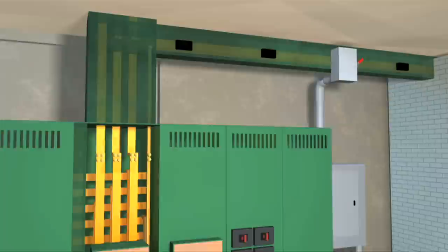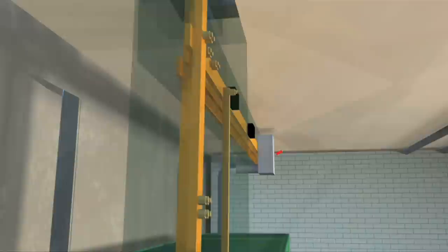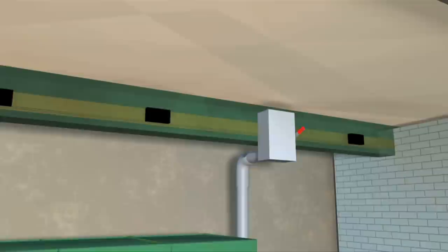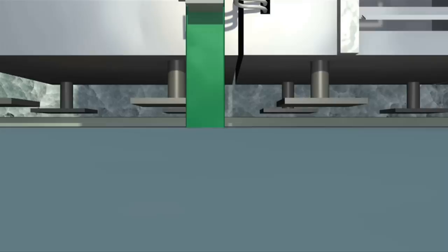Our draw-out breaker in section two is connected to bus duct. Bus duct is a rectangular or square metal enclosure containing bus bar. Its purpose is the same as electrical wire and conduit, but is able to handle larger amp ratings. Bus duct is made up of ten-foot sections. Plugs or connectors are spaced every two or three feet for the purpose of attaching fused disconnect safety switches, which can then supply voltage to designated areas. In our example facility, you see the bus duct rising vertically to the roof. It passes through an electrical room on each floor. These rooms generally house breaker panels, one or more transformers, and or disconnect switches. Power is then distributed throughout the floor. The bus duct reaches the roof to supply power to HVAC systems through a disconnect.